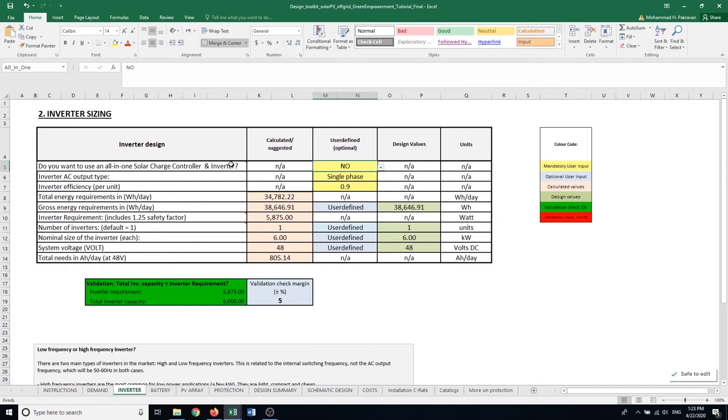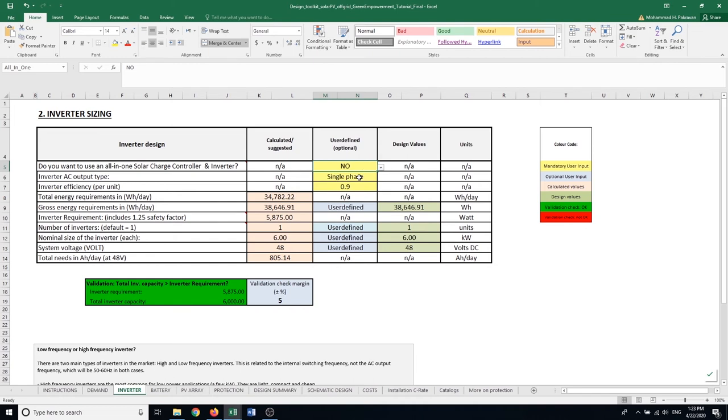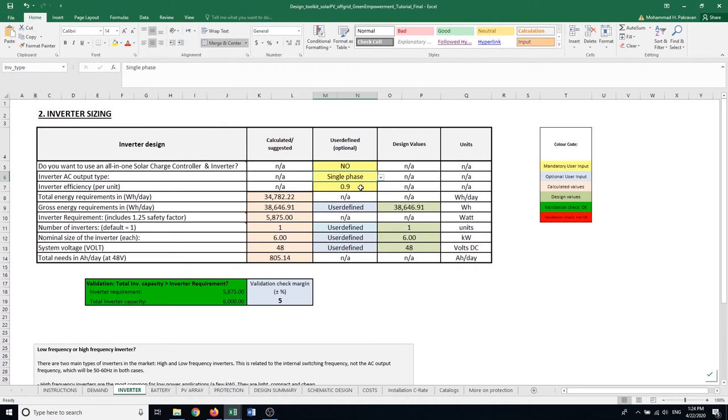In this example, here if we're using an all-in-one solar inverter, solar charge controller and inverter, we put yes. For the purpose of this example, I'm going to design these two equipment separately so I put no. Every single use that I have in my community is basically single phase, so I'm going to use single phase rather than three phase. And the inverter efficiency, I'm going to assume it's 90%. You could change this if you have a particular inverter or inverter brand in mind that has higher efficiency or lower efficiency. The next thing I see here is that the system has calculated based on the inverter efficiency how much gross energy I need in my system.